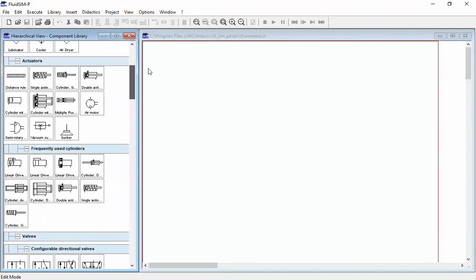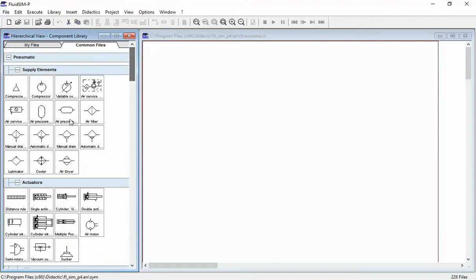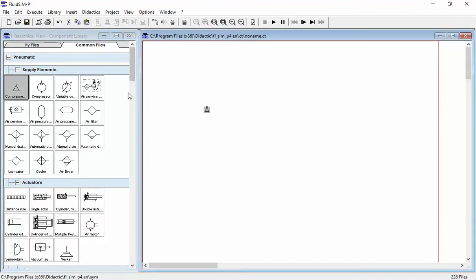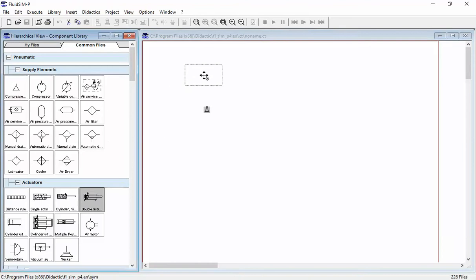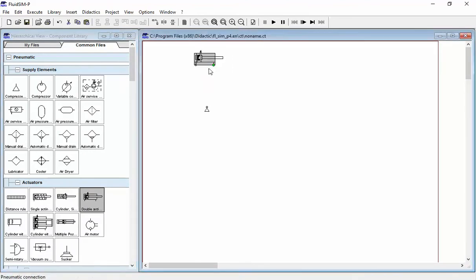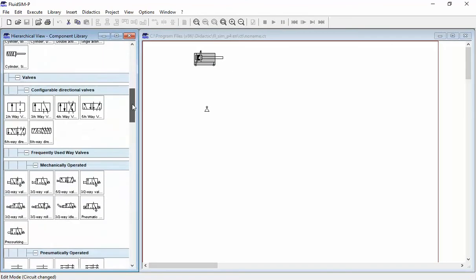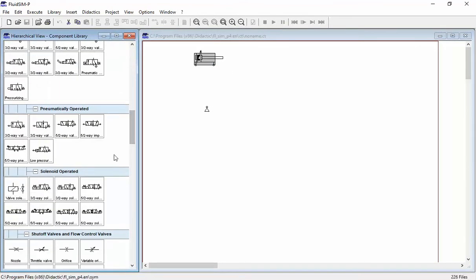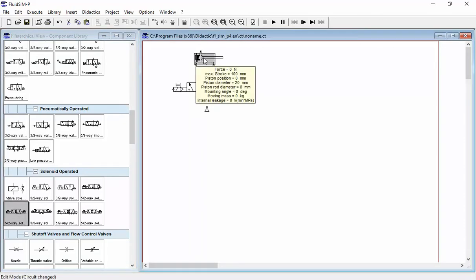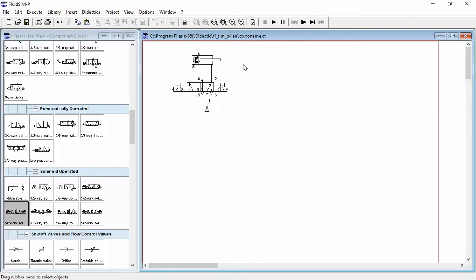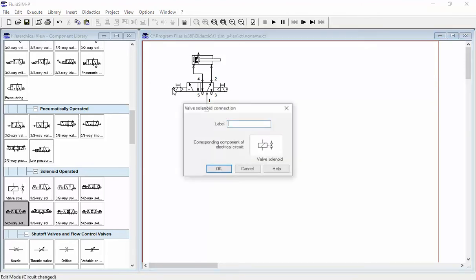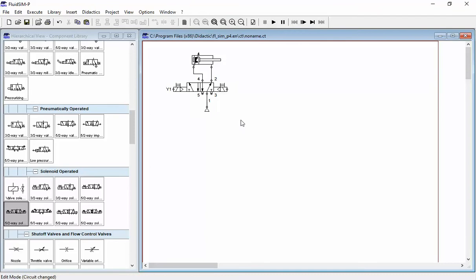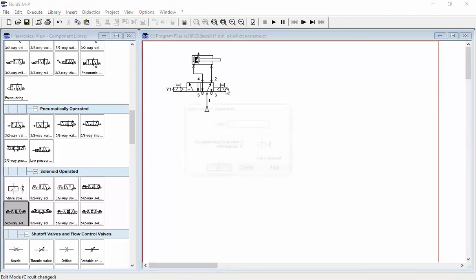First step, I will create a simple pneumatic circuit by using a double-acting cylinder and a 5/2-way valve double solenoid. I will take from supplier to port 1, and from port 2 to create backstroke of the cylinder, and from port 4 to create forward stroke. Here we have two solenoids, Y1 and Y2.